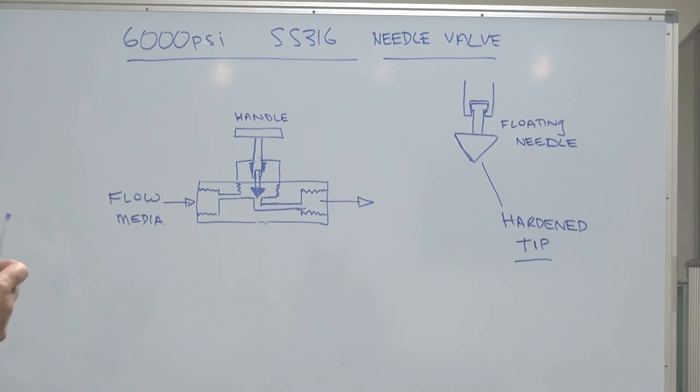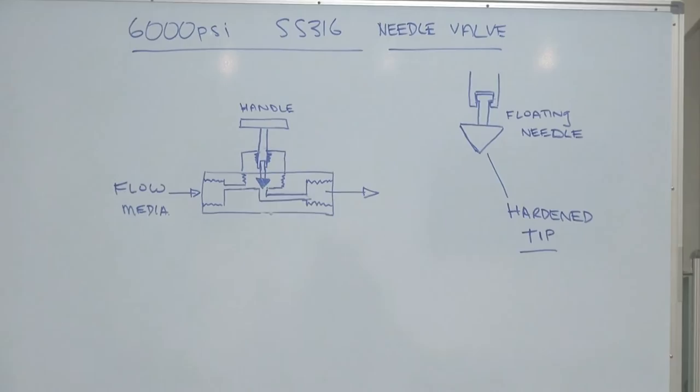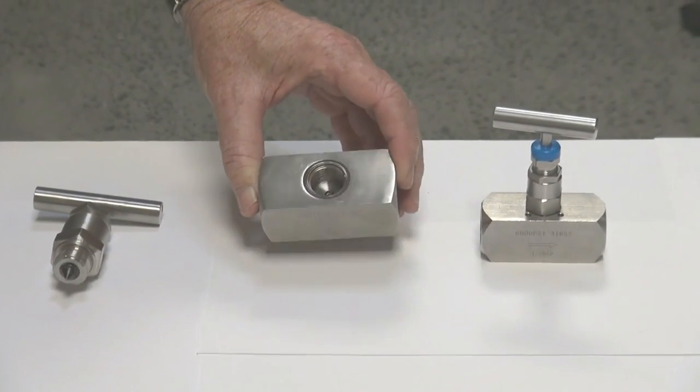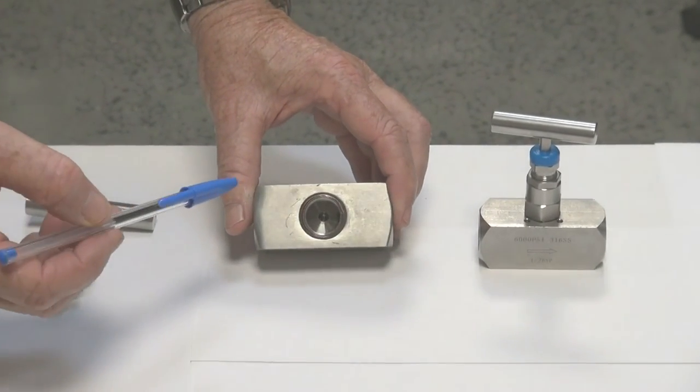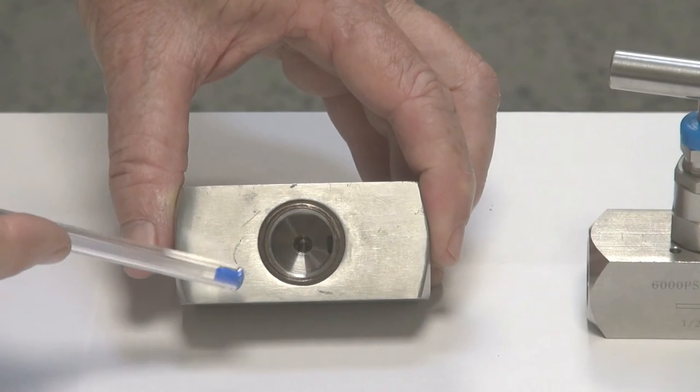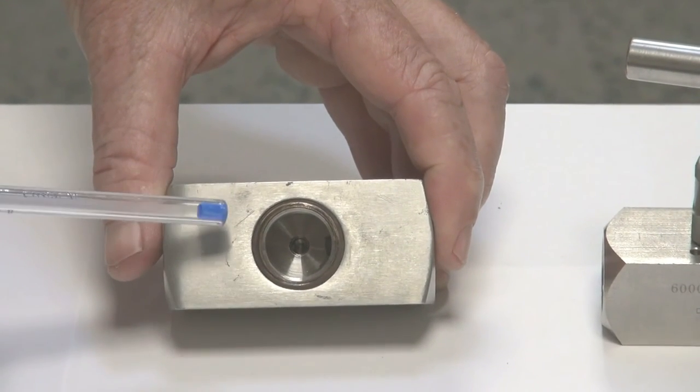Let's go over here now to have a look at the valve in disassembled form. If you look into the top, you can see the orifice inside - in this case, about a five-millimeter orifice. The flow is in the direction shown through here.